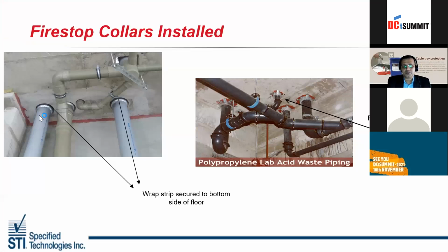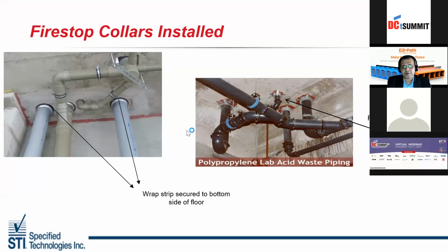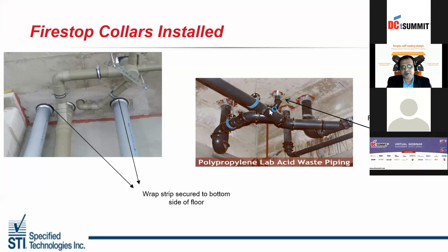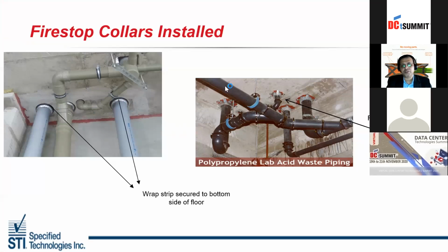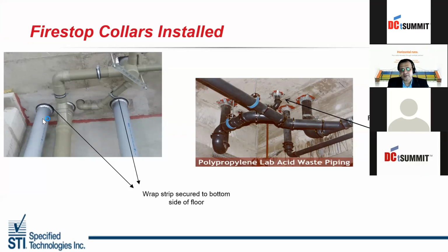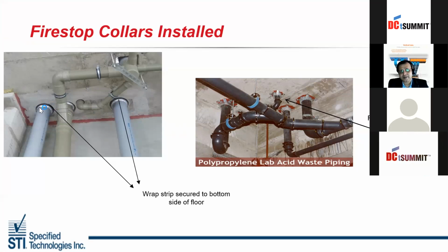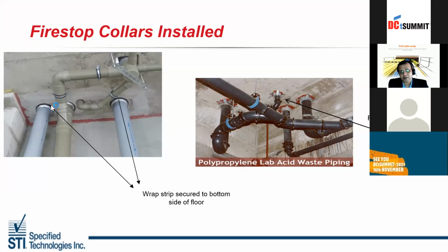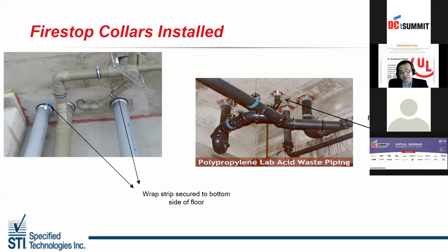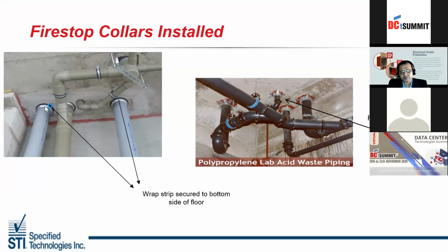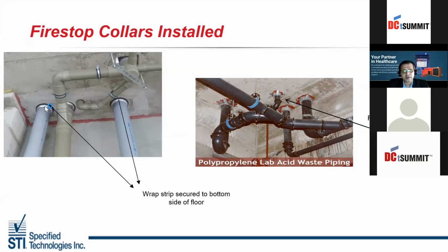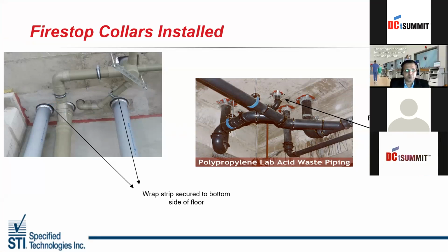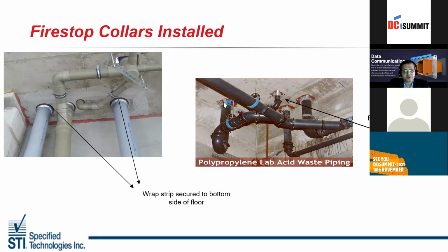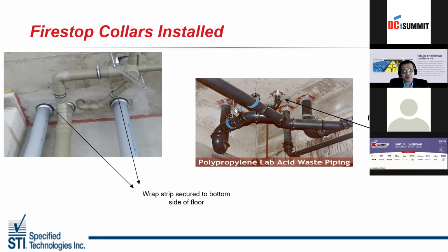Here I'm showing you scenarios where you have a 4-inch pipe with a sleeve, with a core cut done. And here you have a 4-inch and a 2-inch pipe, but there is no core cut. The difference is that when a core cut is done, you can easily install the wrap strip between the floor and the pipe. In case of fire, the concrete will support the wrap strip in closing the pipe with the intumescent. Where you don't have a core cut done, we can install the complete wrap strip in this kind of scenario.